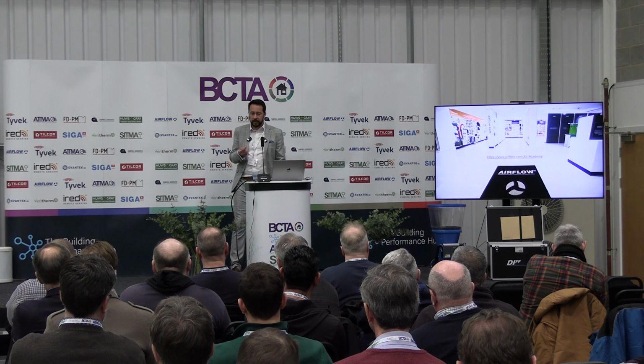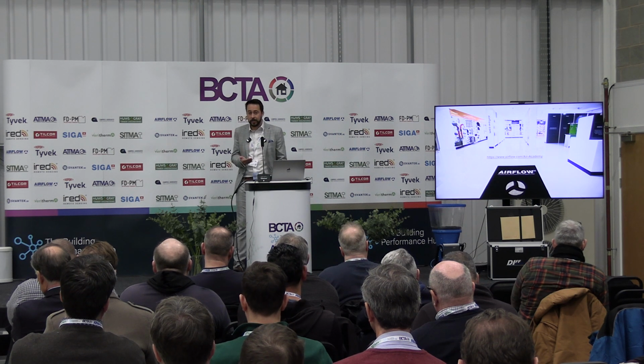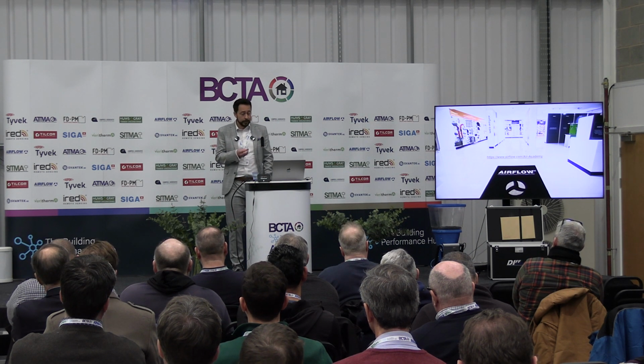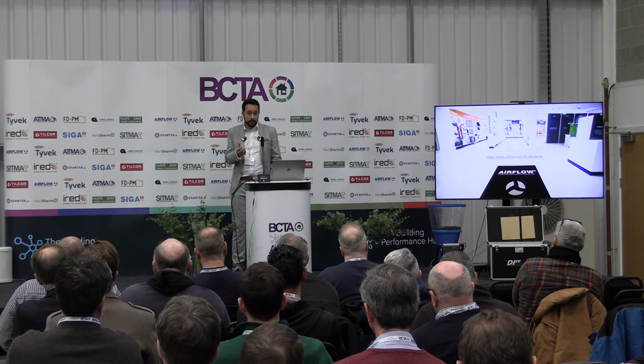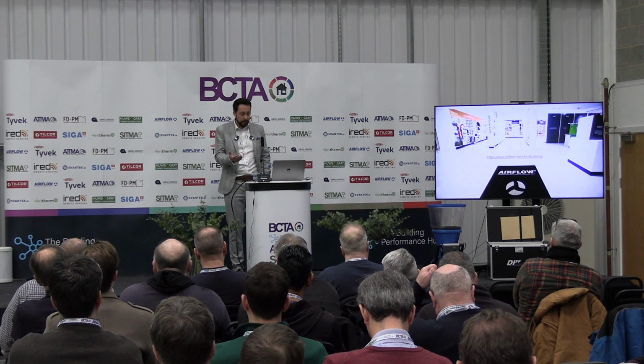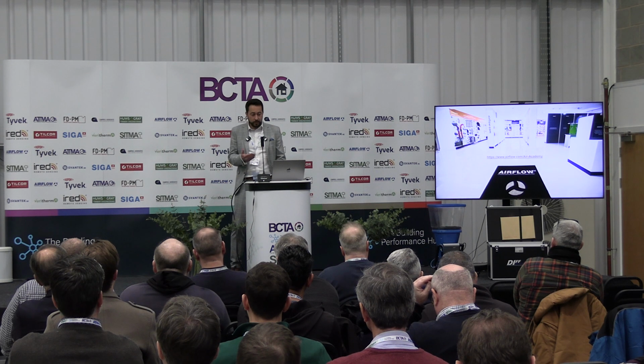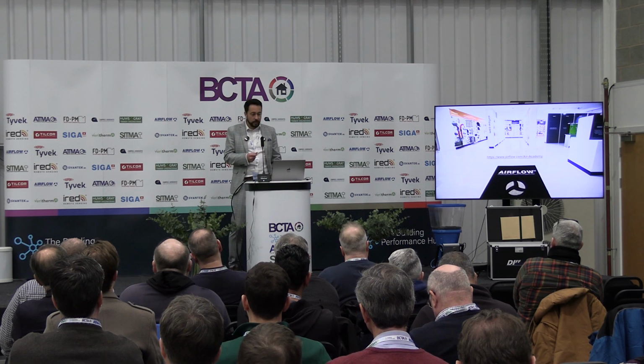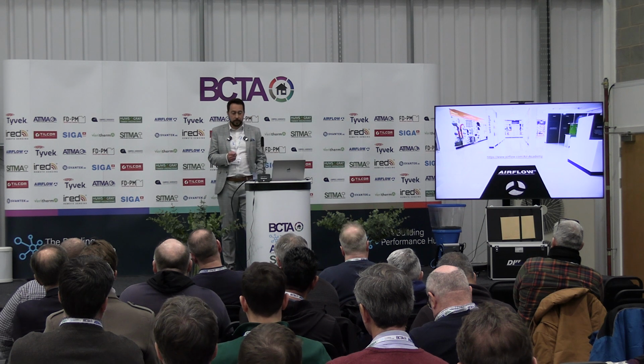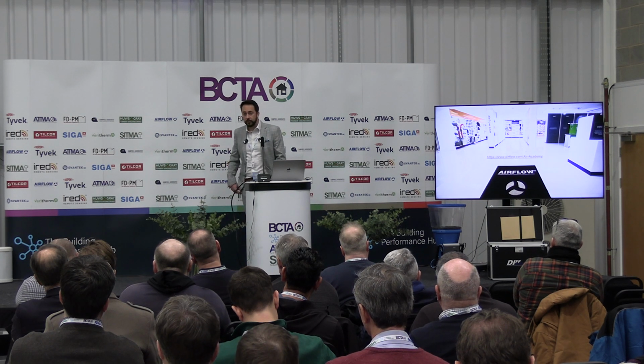It is important to note there are other products out there that have a summer bypass facility, but it's a manual process. So it then relies on the homeowner or the owner of the building to manually go and open or close that summer bypass. And we know at the moment in industry, MVHR isn't that familiar to most homeowners. So if it is a manual process that is relied upon, I think at the moment we can be pretty certain that most homeowners are not going to know when to turn it on or turn it off. So it's better to have that automatic bypass in place. So yes, you do get your heat recovery and cool recovery.